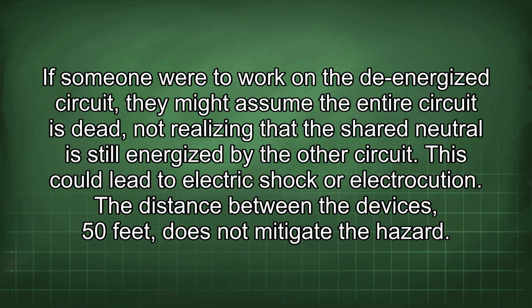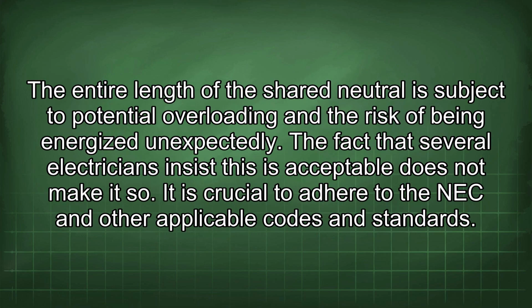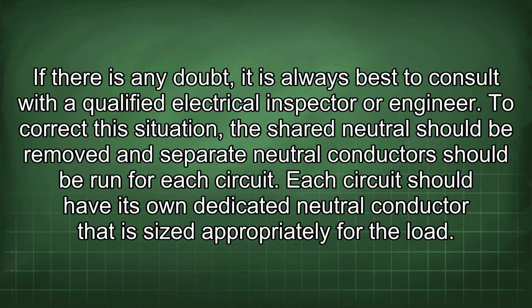The distance between the devices, 50 feet, does not mitigate the hazard. The entire length of the shared neutral is subject to potential overloading and the risk of being energized unexpectedly. The fact that several electricians insist this is acceptable does not make it so. It is crucial to adhere to the NEC and other applicable codes and standards. If there is any doubt, it is always best to consult with a qualified electrical inspector or engineer.